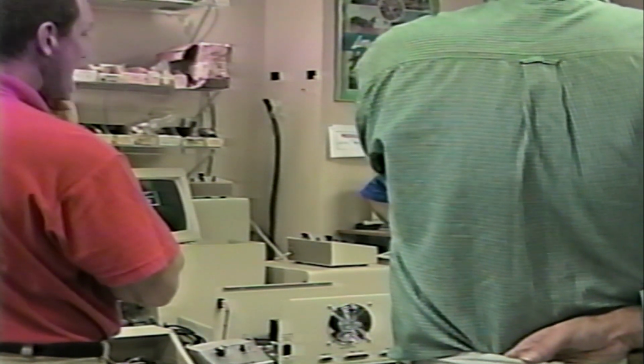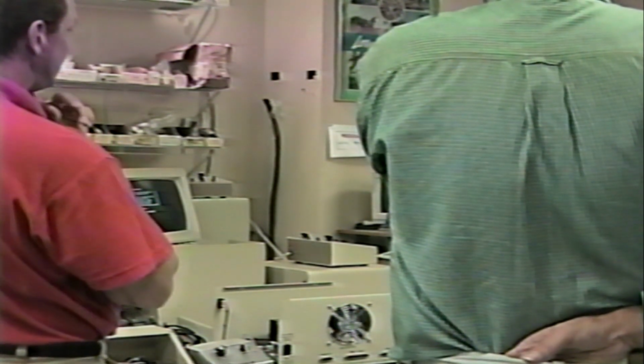What can happen is this motor overheats, and the signals don't come through clearly, which can cause unpredictable results. In other words, it may not raise all the way back up to the home position every time, and eventually by the end of the plate it's dragging, or it may possibly not go all the way down to the table.